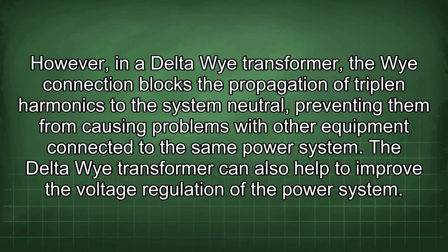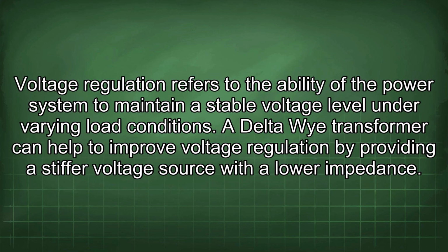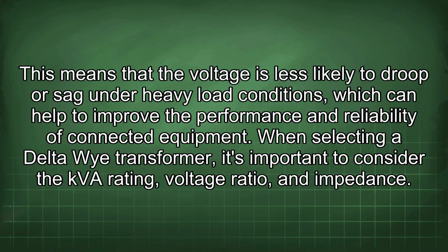The delta Y transformer can also help to improve the voltage regulation of the power system. Voltage regulation refers to the ability of the power system to maintain a stable voltage level under varying load conditions. A Delta Wye transformer can help to improve voltage regulation by providing a stiffer voltage source with a lower impedance. This means that the voltage is less likely to droop or sag under heavy load conditions, which can help to improve the performance and reliability of connected equipment.